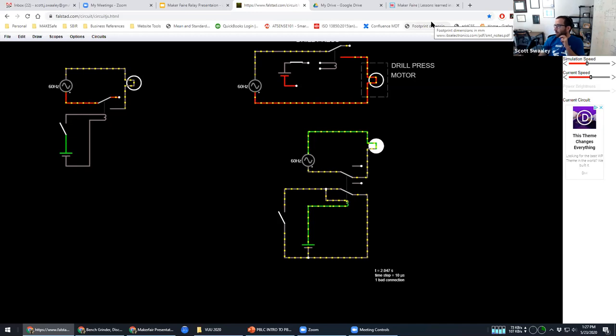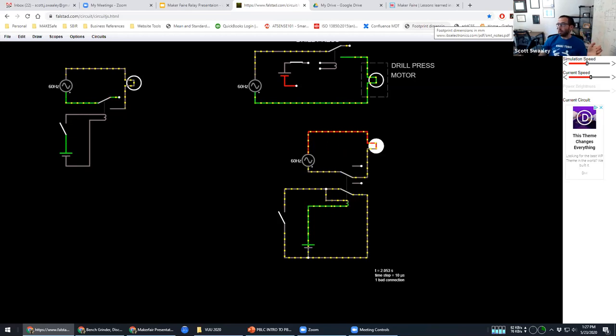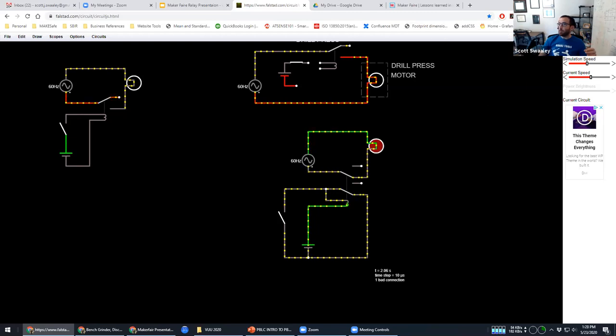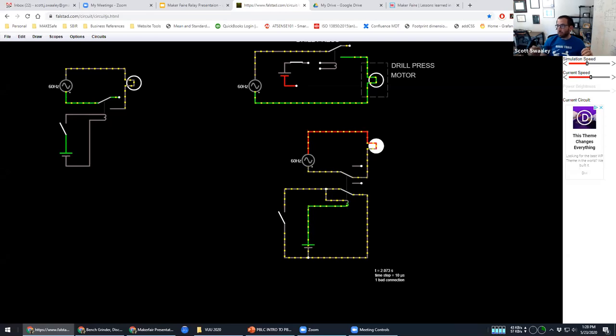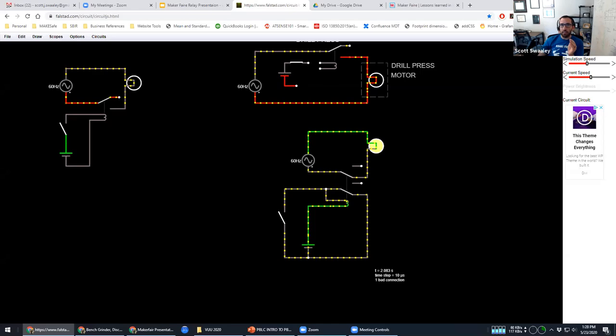So Peter says he's seen a lot of relays where the contacts go bad over time because of arcing. So I'm going to talk about that a lot in my next session in just a few minutes. The short answer is that's people using relays that aren't rated for what they are using them for. And the number one reason is inductive load. So I was talking about with motors that you want to make sure they have a horsepower ratings. If you don't have a horsepower rating, what will happen is when that relay tries to separate, right? There's two pieces of metal in that relay that at some point want to separate to open the circuit. If it's an inductive circuit, like a motor, that circuit doesn't want to open and it will fight by creating a high voltage. So that's going to actually pull apart and create basically a welding arc. And that can destroy contacts instantly, or slowly over time, depending on the load. So that's all for this quick one.